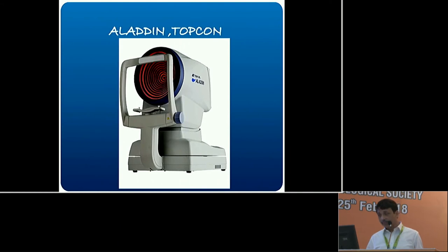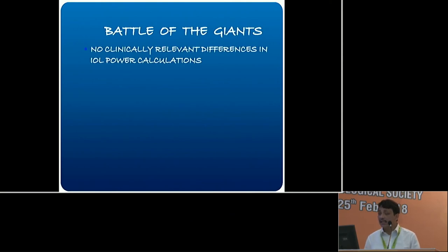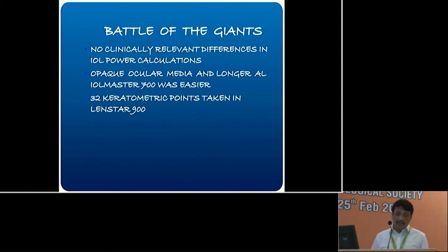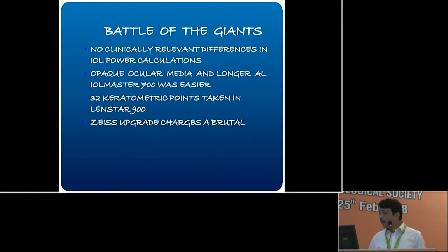The Aladdin from Topcon is also doing well — these are the top three options. Comparing the Lenstar versus the IOL Master 700, data tells us there are no clinically relevant differences in IOL power calculations — they're almost similar. But in opaque ocular media like vitreous hemorrhage, dense lens opacities, or longer axial lengths, the IOL Master 700 seems easier and faster. One main advantage of the Lenstar is that it takes 32 keratometric points in two circles for very precise keratometry. Unfortunately, the software upgrade charges are steep.